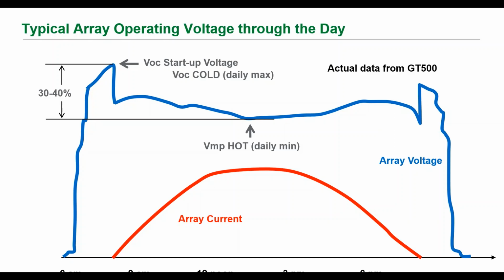Like if you want a 1000-watt system, a 1 kilowatt system, and the voltage is 1000 volt, the current will be only 1 ampere, and your losses will be directly proportional to current. That is I squared R loss. Heat loss is nothing but I squared R loss. So the lesser the current, the lesser will be the I squared R loss, and the more will be the efficiency. So to reach that, we go to higher voltage, but we can't increase the voltage beyond a certain limit, because the insulation is important and the safety is also important. So we need to strike a balance between voltage and current, so that 1000-volt is somewhat acceptable from a safety perspective, and also good for improving the efficiency.